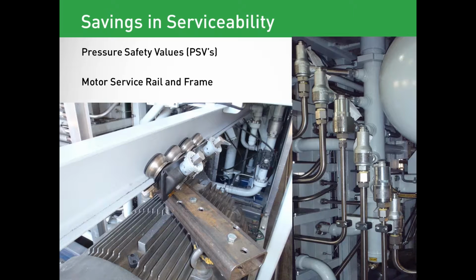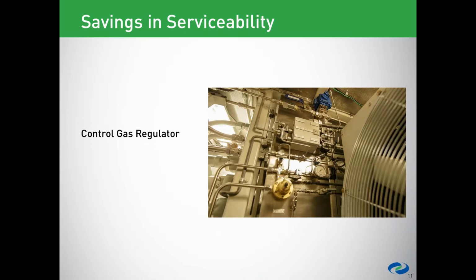And finally, the control gas regulator has been relocated at the end of the service corridor for ease of access, and in addition, a transmitter has been added to the system such that the control gas pressure can be monitored. Warnings and alarms can be triggered based on high and low control gas pressure for immediate access and easy troubleshooting of loss of pressure if required.